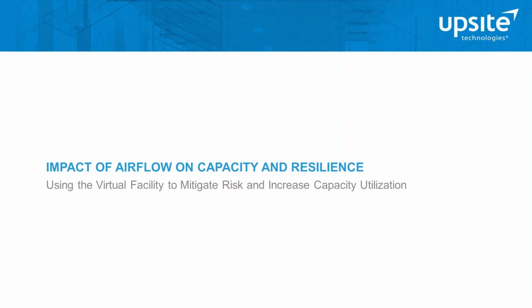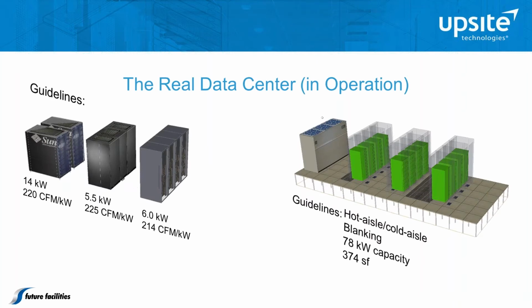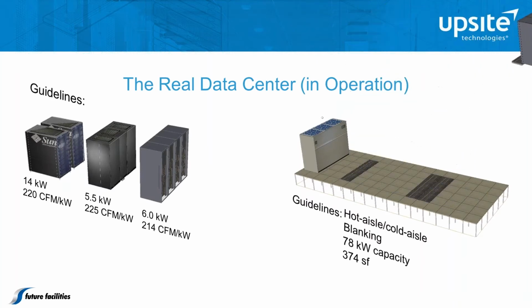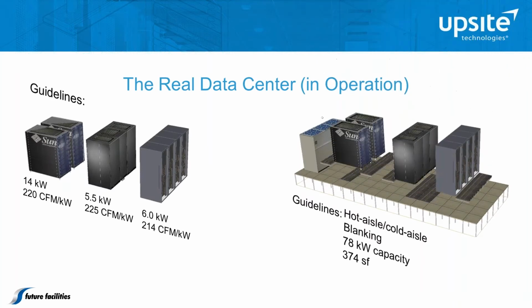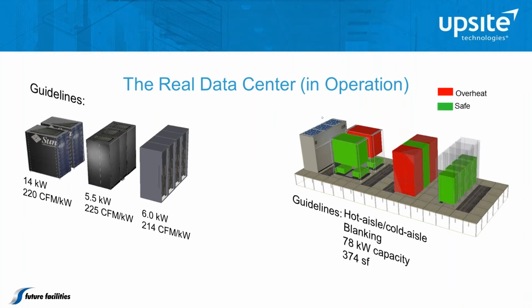The problem you see in front of you is that 3 of those cabinets have suddenly overheated. As far as the fragmentation of space and power is concerned, that's controllable, measurable, quantifiable. Unfortunately, the fragmentation of cooling is impossible to predict, mainly because cooling is dominated by airflow, and airflow is invisible. So when you fragment airflow, the complexity of the situation, the physics of it, is impossible to predict unless you calculate it.